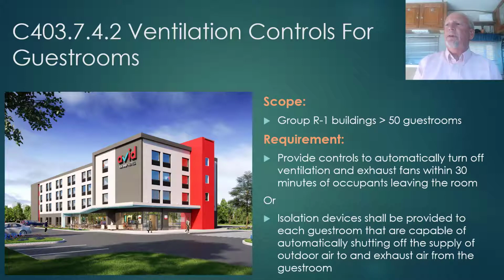A few more control things worth noting. If you're involved with permitting or designing of hotels and motels greater than 50 guest rooms, this will have an impact. So Group R buildings greater than 50 guest rooms, we've had a requirement in the code for these larger Group R1 buildings to have some sort of automatic control of the heating and cooling in the guest room. When the guests leave, it shall be automatically controlled either through key card or other sensor. That control has now expanded to the exhaust system that serves that guest room. So in addition to reducing the heating and cooling, you shall now provide controls to automatically turn off the ventilation and exhaust fans within 30 minutes of the occupants leaving the room.